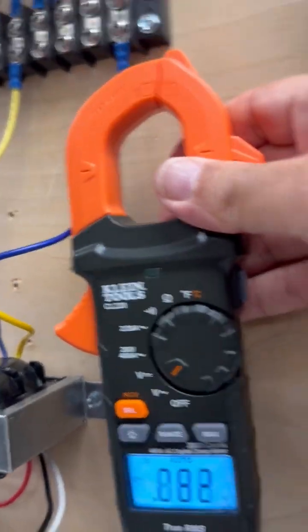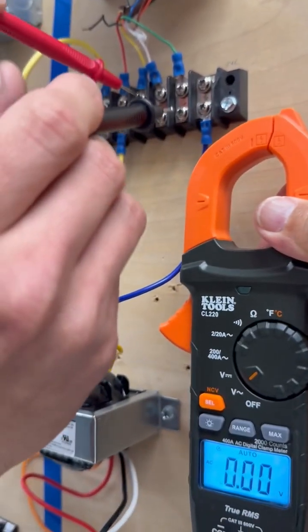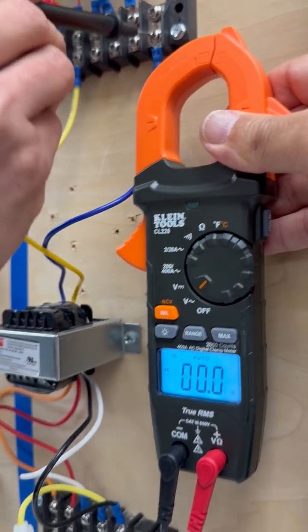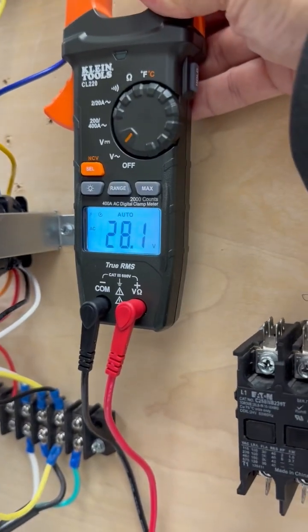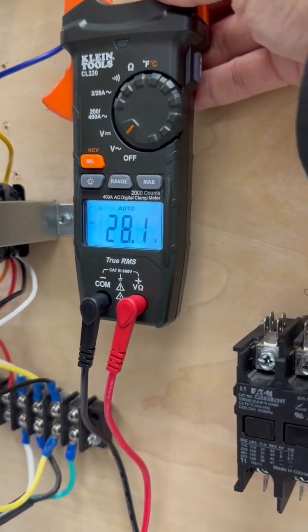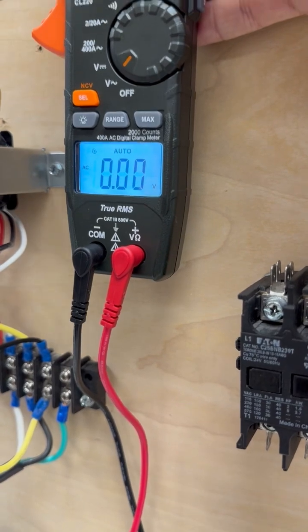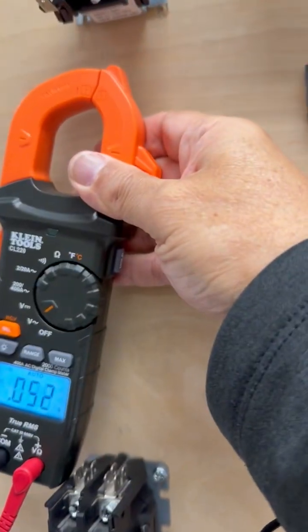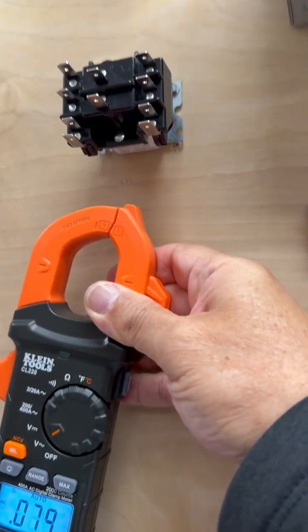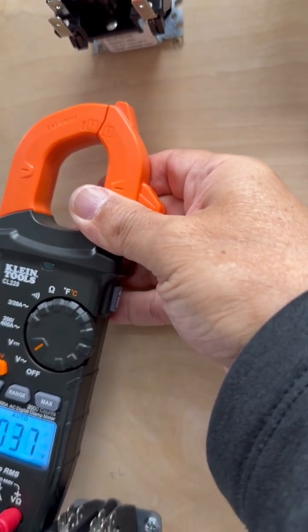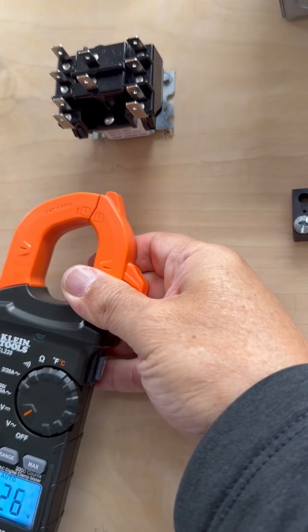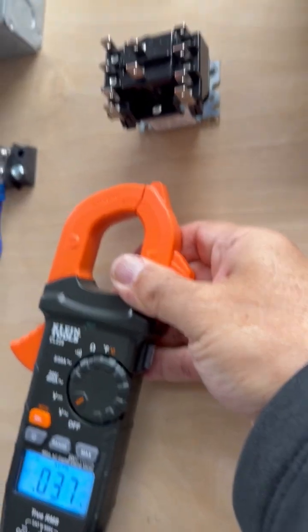Now in particular, we're supposed to get a reading from yellow to one of the hot legs on the secondary side of the transformer. So now this voltage feeds into the coil of this relay here, this contactor. And then from there, pin 1 will close, and then pin 3 will feed out a voltage to, say, a cooling system or a unit.